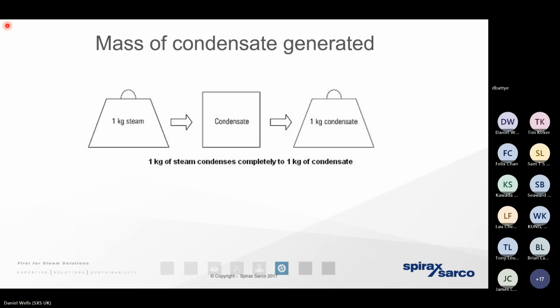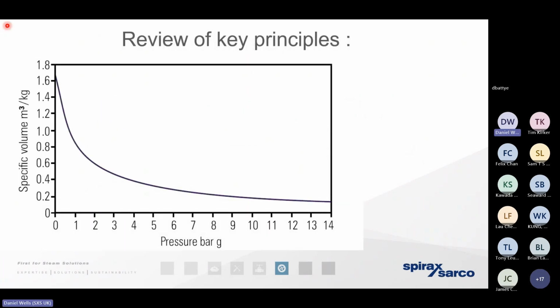regardless of the volume. And then when that steam gives up its heat energy and condenses, its phase changes again. It's changing from a gas back to a liquid. And again, the mass remains the same. The only variable is the volume that the steam exists at, and that is dictated by the pressure that the boiler's operating at. And that's really one of the reasons why we always refer to a system by a mass flow rather than by a volumetric flow. The volume will change, but the mass will remain constant regardless of the state and regardless of the operating pressure. So I've also gone through that pressure volume relationship.